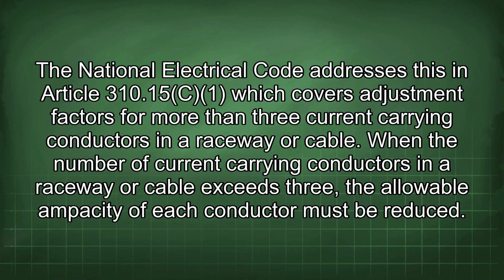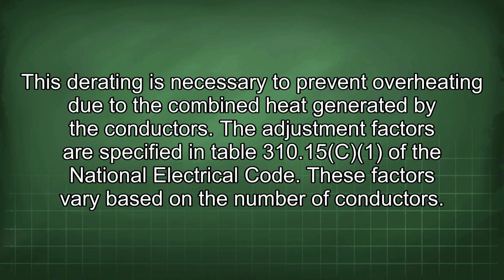The National Electrical Code addresses this in Article 310.15(C)(1), which covers adjustment factors for more than 3 current carrying conductors in a raceway or cable. When the number of current carrying conductors in a raceway or cable exceeds 3, the allowable ampacity of each conductor must be reduced. This derating is necessary to prevent overheating due to the combined heat generated by the conductors. The adjustment factors are specified in Table 310.15(C)(1) of the National Electrical Code. These factors vary based on the number of conductors.